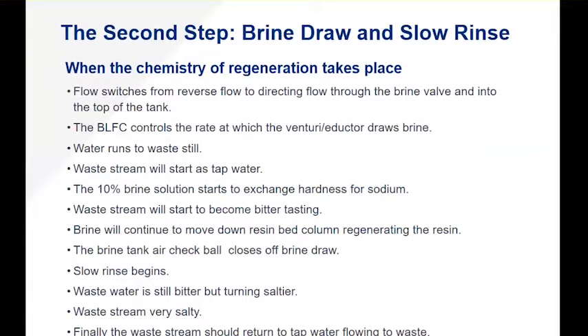At the point when we've drawn all the brine out of the brine tank, there is an air check — either in the tank, in the case of a Fleck valve, or up in the head in the case of some of our Autotrol valves. This ball will then seat and seal off whatever remaining water is in the brine tank so we don't draw air into the resin tank. At this point, we've converted over from brine draw to slow rinse — the water is still going through the injector, but it's nothing but tap water, slowly rinsing out any built-up or excess salt.